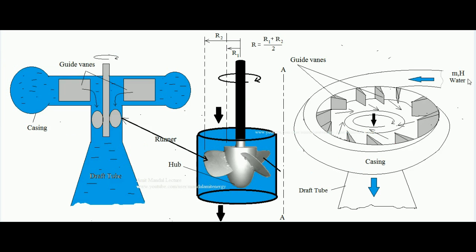This is the detailed diagram of the Kaplan turbine. You can see water coming from the penstock first reaches the casing. After the casing, water passes through the guide blades. The guide blades direct the water at a particular angle so that it develops a whirl — a rotational motion — in the water. Ultimately the water reaches the center and falls in an axially downward direction.